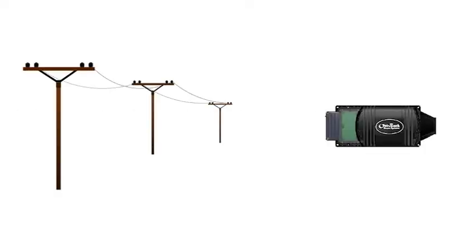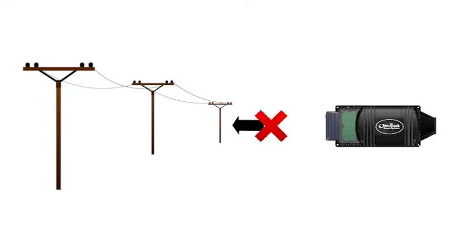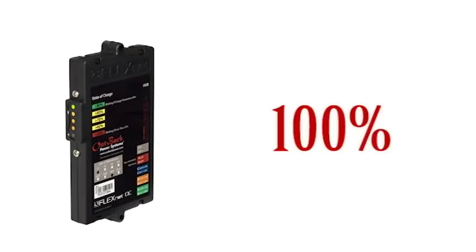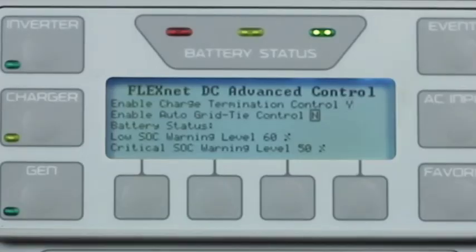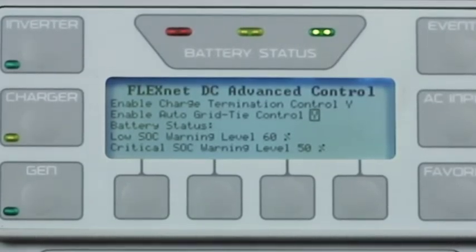The second one is Auto Grid Tie Control. This feature is only operative when you have grid interactive inverters in your system. This feature will command all the inverters to turn off the Sell feature every night at midnight and will not turn it back on until the FNDC has met its parameters. To enable this feature, change the value to Y. Or to disable, change it to N.